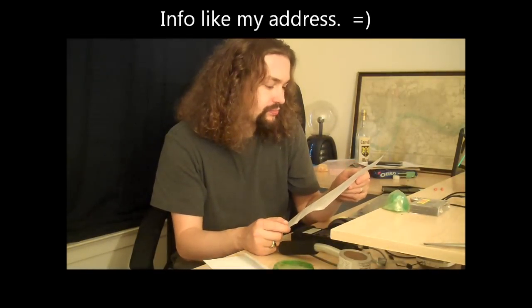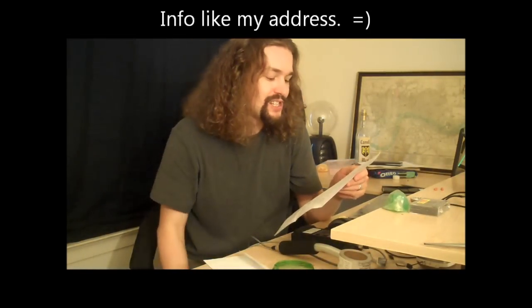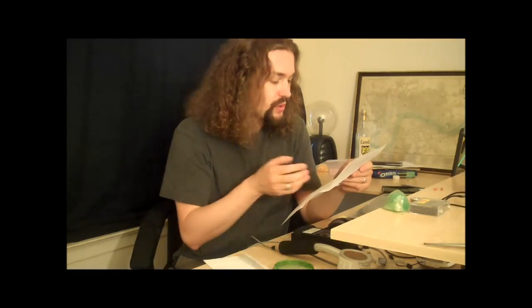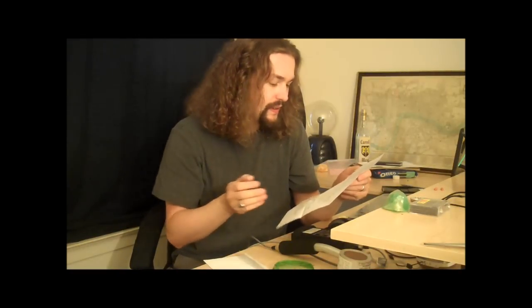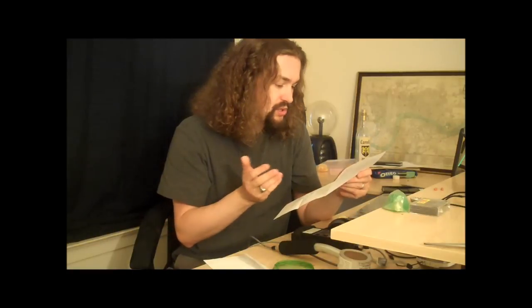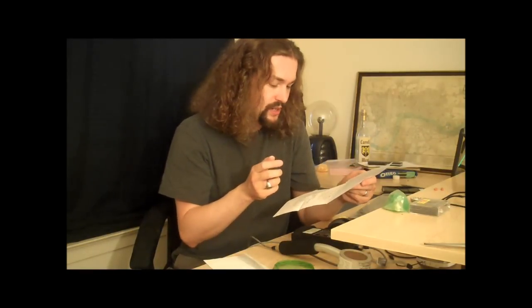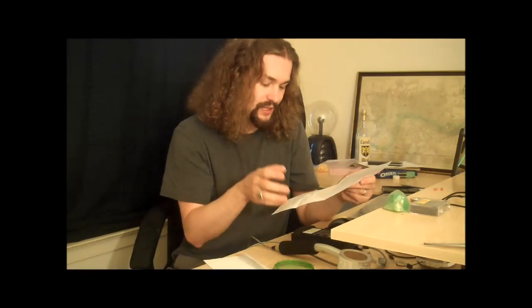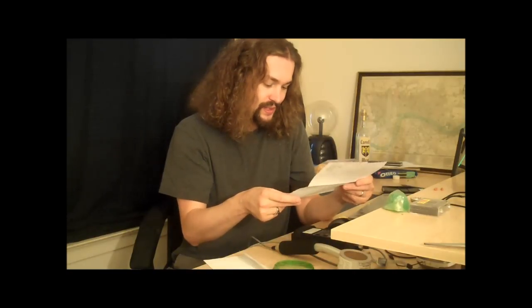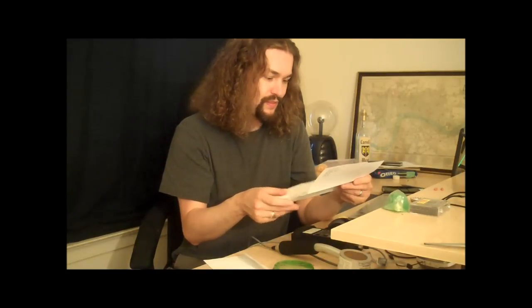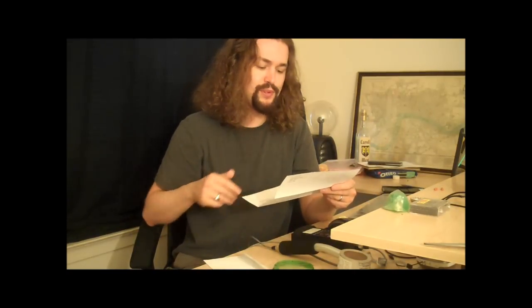It says precision consistency check performed with CS137 source, serial number for the source included. Reading 1, reading 2, reading 3, the mean reading, plus or minus what it came out to, how much was used, the exact date, all the times, everything that goes with it. This is awesome—they even told me my 9-volt battery is producing 9.38 volts DC.